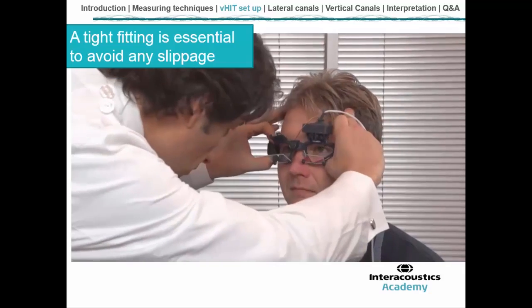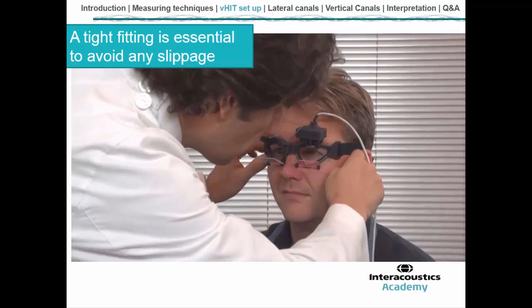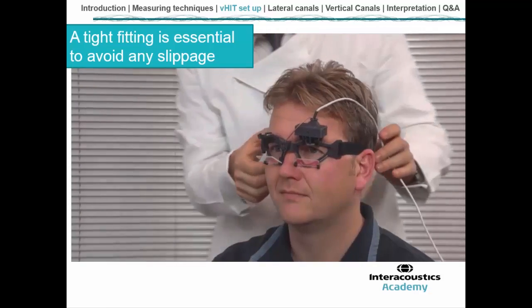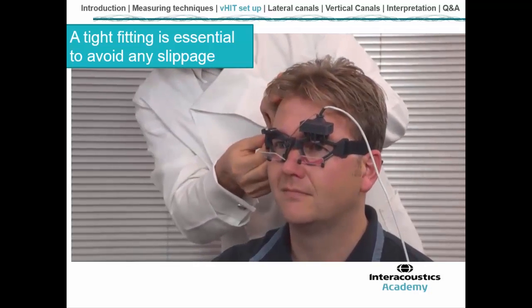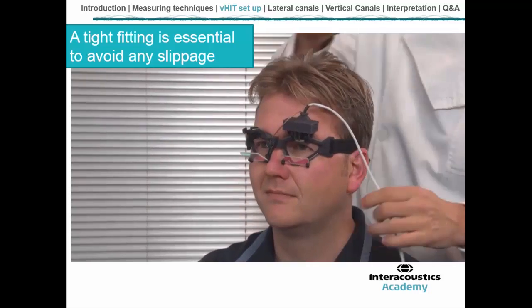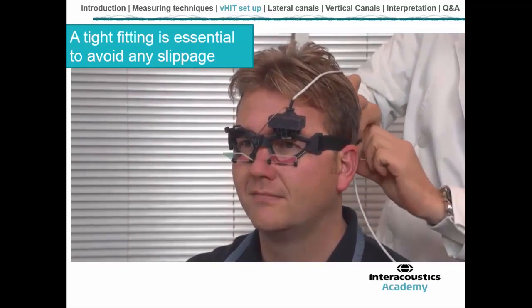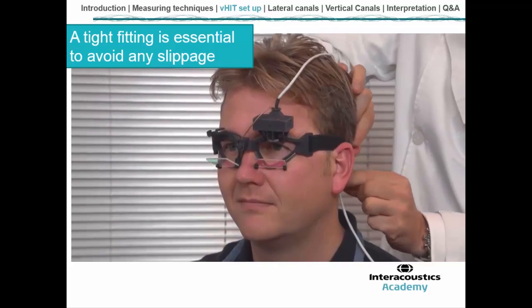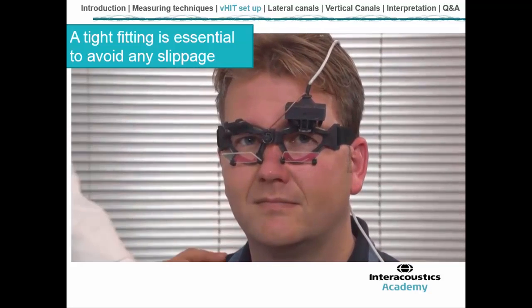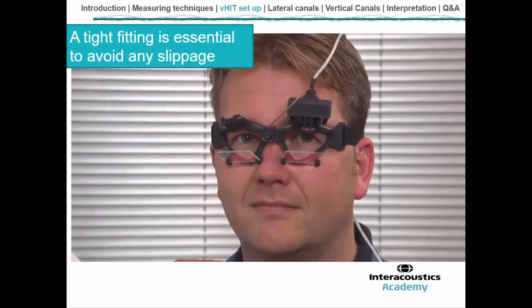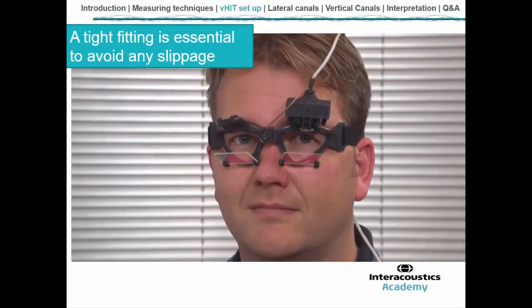And what we can see is that he's firstly lining the goggle up so that the camera's facing and looking at the eye. He's then going to come round to the strap on the side and tighten it so it's nice and tight, so that there's not going to be any slippage. Lastly, he takes the USB cable and places it in the USB cable holder. It's really important that you don't want the USB cable to be flopping around or to be touched during the head impulses testing, as this can pull on the goggle and also introduce artifact. But when the goggle's set up like this, it did not take very much time at all. We can see that we are ready for testing.